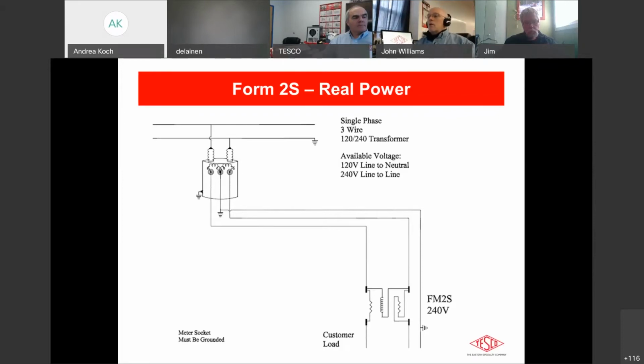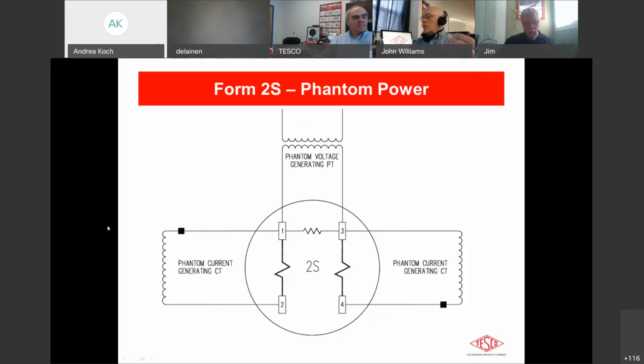Now that being said, the newer test boards, like I talked about before, with all these digital sources and processors and software and all that fun stuff, you can set them up to act differently. You can test the meter with an imbalanced load. You can test offset voltages, you can test offset currents, and still do a simple accuracy test based on those conditions. If any of you are interested in real life testing of Blondel's theorem, you can do that with the TESCO test board, for instance.